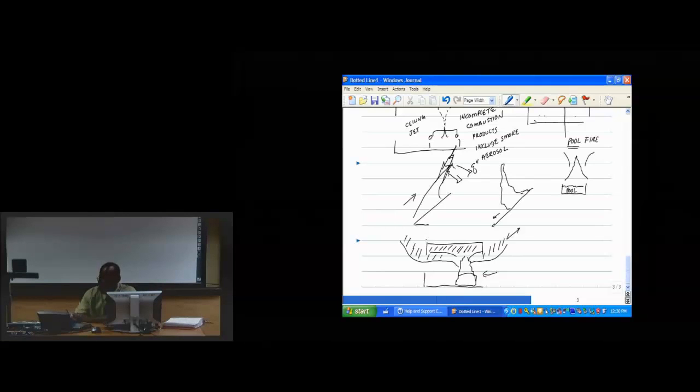Again, this is going to be considered a very high temperature upper layer. So T upper is larger than the lower layer temperature, and there's a lot of thermal radiation. That's because we have this dark, hot cloud of smoke and products in this upper layer that are radiating throughout on all the different parts of this compartment.